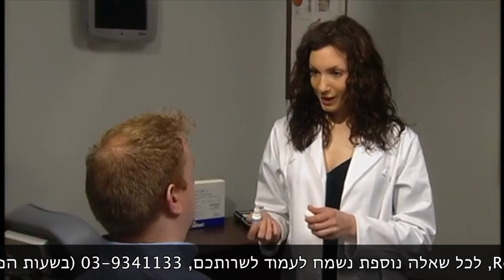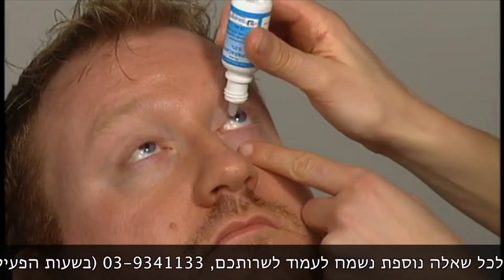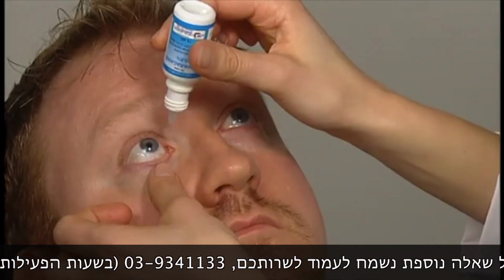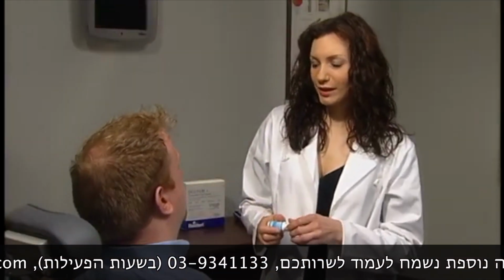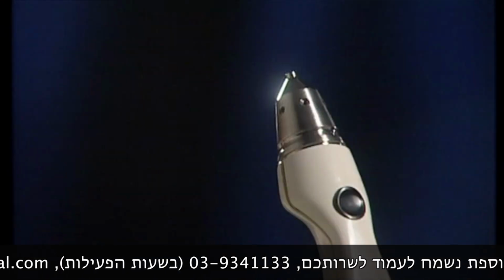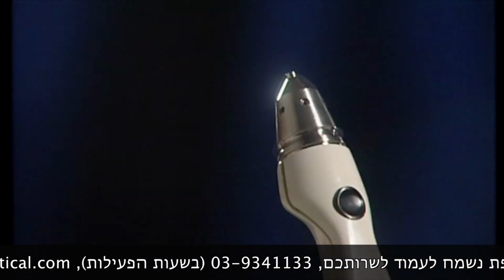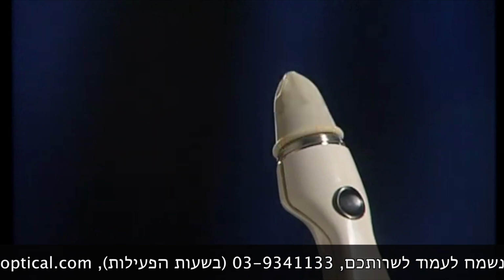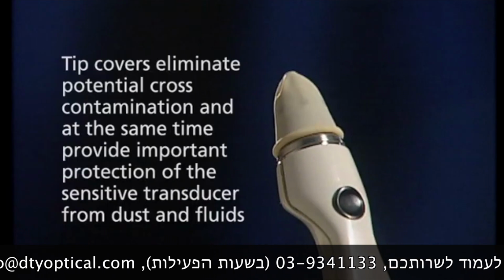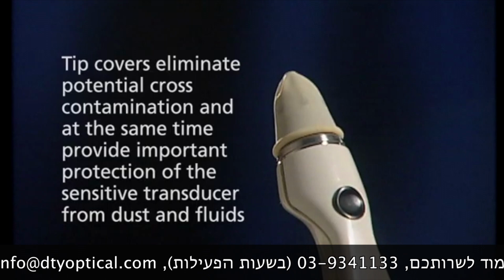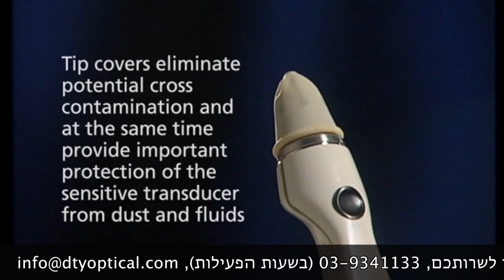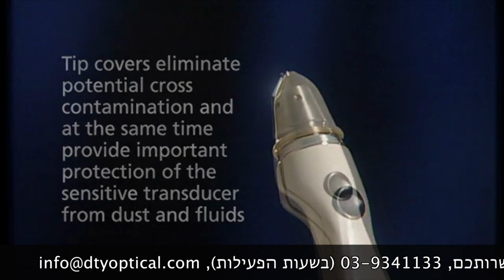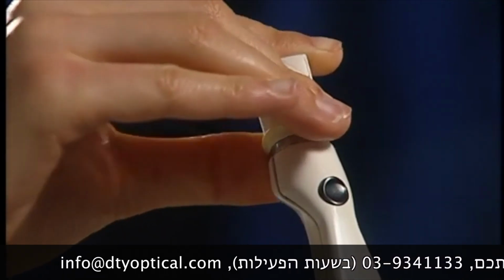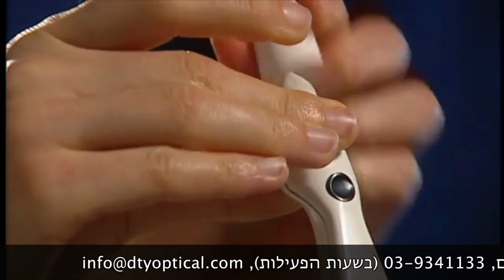The first step is to anesthetize the patient's cornea by the application of a topical anesthetic. The next step is to prepare the TonoPen XL tonometer for use by placing a sanitized tip cover on the transducer. Tip covers eliminate potential cross-contamination and at the same time provide important protection of the sensitive transducer from dust and fluids, and they are very easy to use. They are simply rolled on using the integrated cardboard applicator, like this.